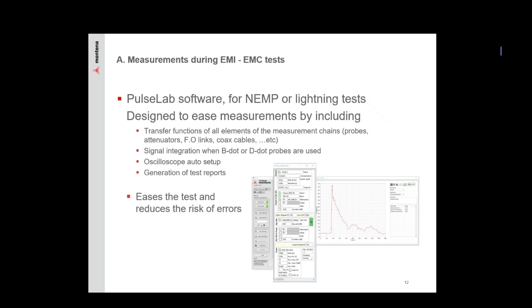Montena has also developed, going back to lightning and electromagnetic pulse testing, the Pulse Lab software for doing measurements. Transfer functions of the measurement chain can all be entered—probes, attenuators, fiber optic links, coaxial cable—along with signal integration when using differential derivative sensors, magnetic or D-dot, since you're measuring the change in current or field, which must be integrated to recover the pulse or measurement you want. Pulse Lab also helps with oscilloscope automatic setup and generation of test reports.